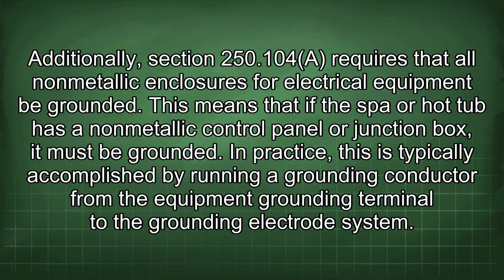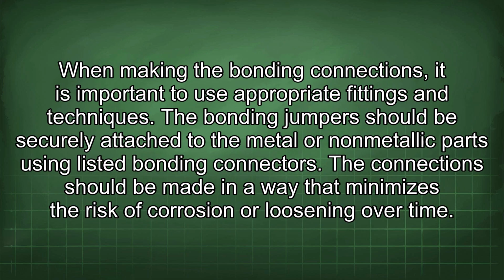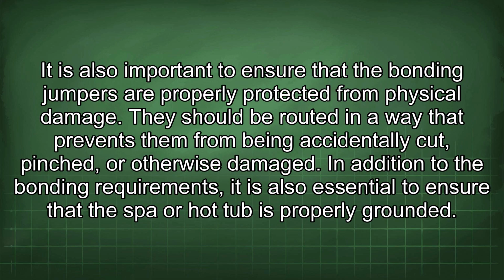When making the bonding connections, it is important to use appropriate fittings and techniques. The bonding jumpers should be securely attached to the metal or non-metallic parts using listed bonding connectors. The connection should be made in a way that minimizes the risk of corrosion or loosening over time. It is also important to ensure that the bonding jumpers are properly protected from physical damage.